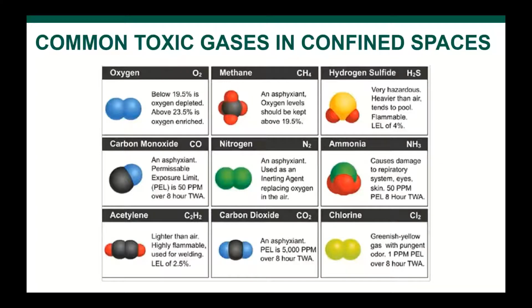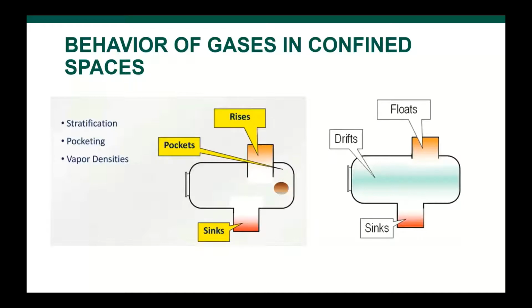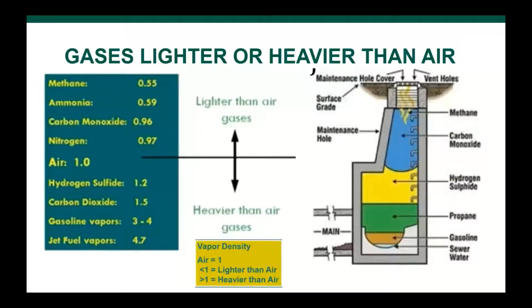So what happens with these gases inside of a confined space? Well, depending on their weight, they're going to either accumulate at the bottom of the confined space, or they're going to rise to the top of the confined space. Some of them are going to drift right in the center, and some of them can cause pockets in certain areas of the confined space. But why is this? Well, some gases are lighter or heavier than air. Nitrogen is really close to air, so it's going to stay around the center of the confined space, more or less. But methane is a lot lighter than air, so it's going to rise to the top of the confined space. But carbon dioxide or gasoline vapors, especially the gasoline vapors, are going to be towards the bottom of the confined space. And this is important to know.